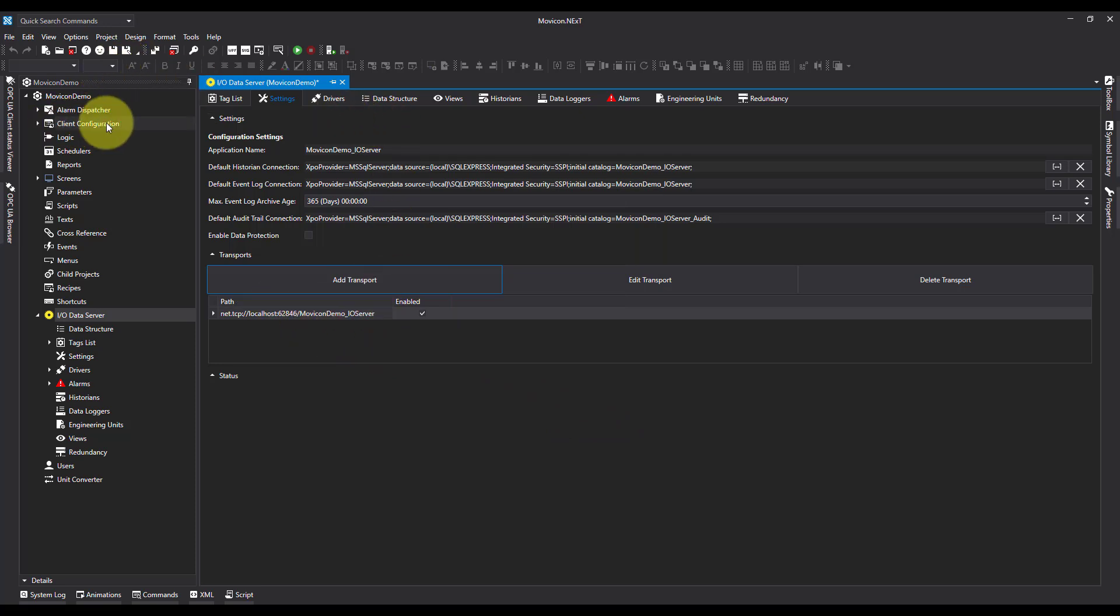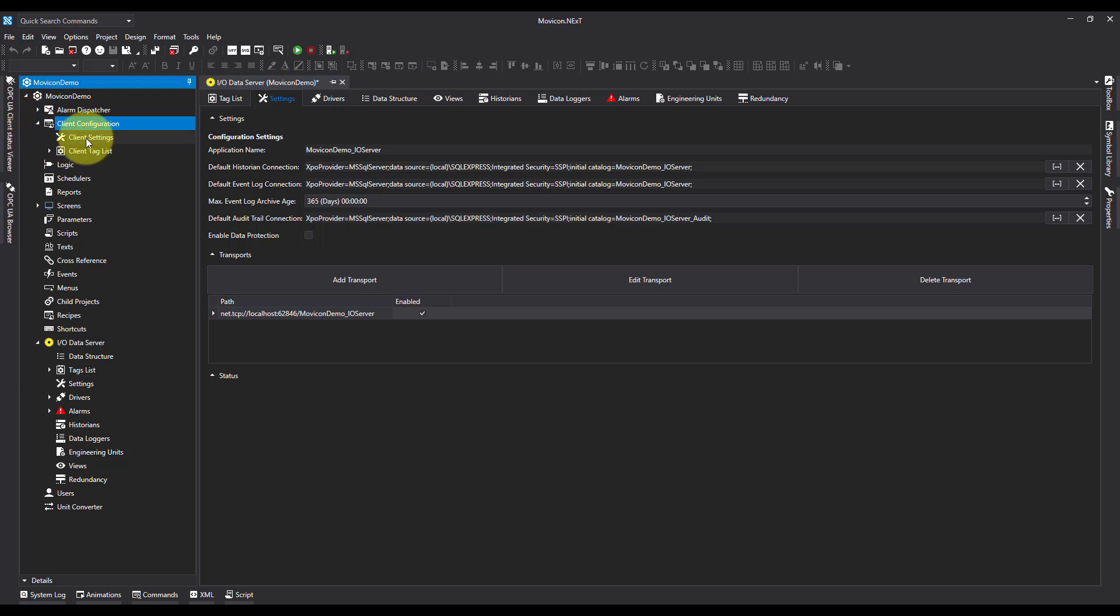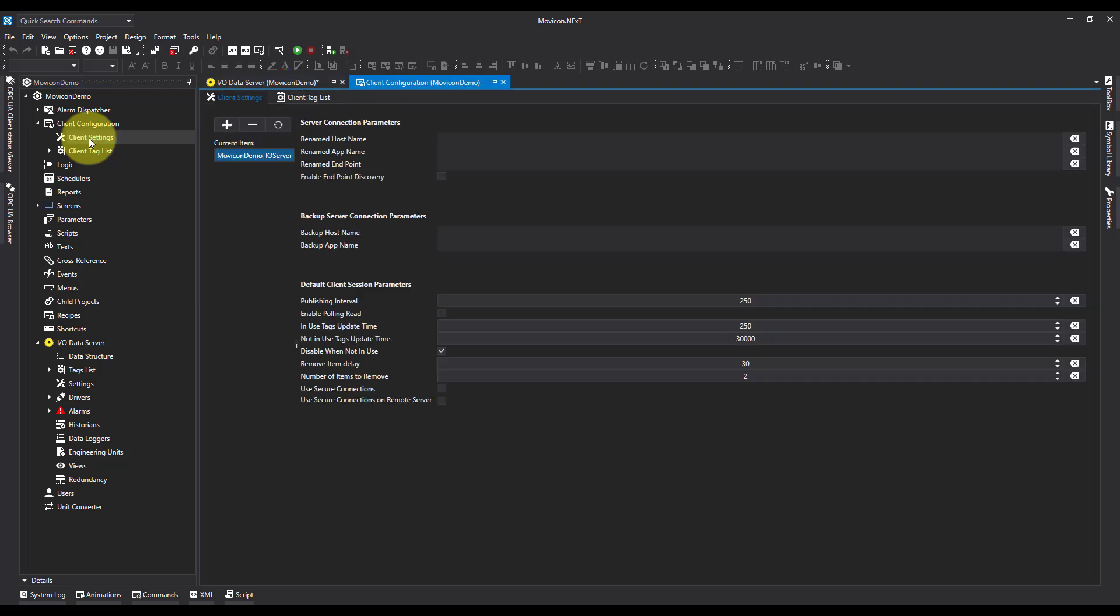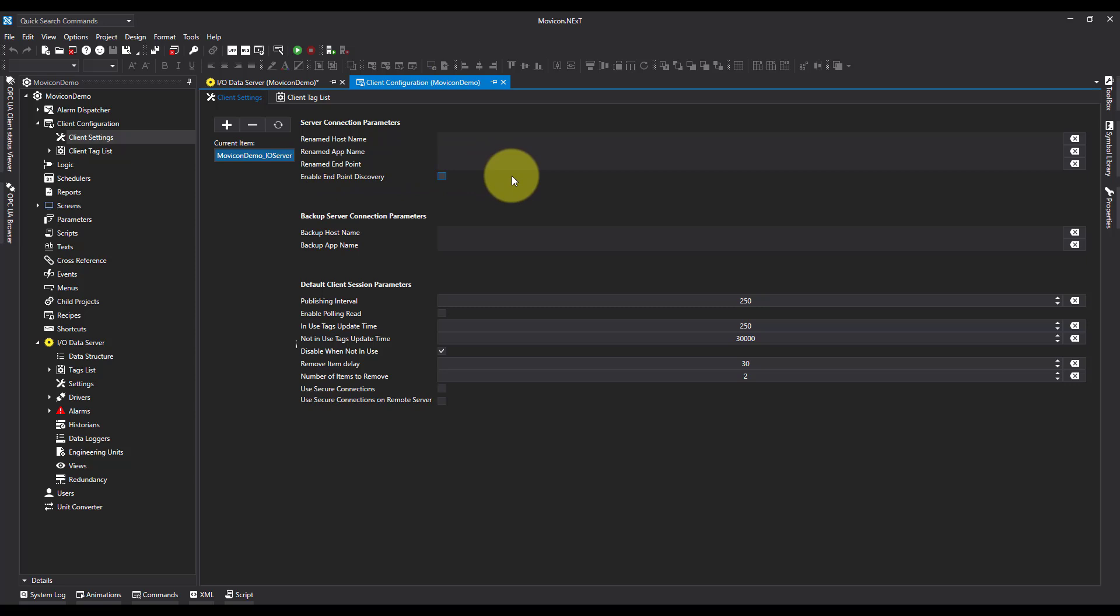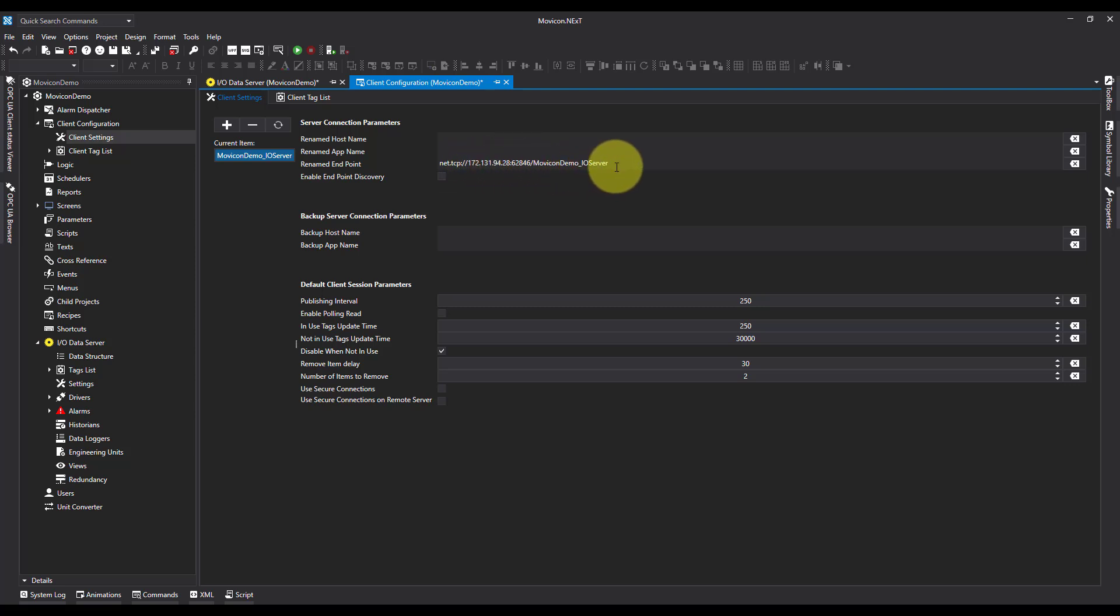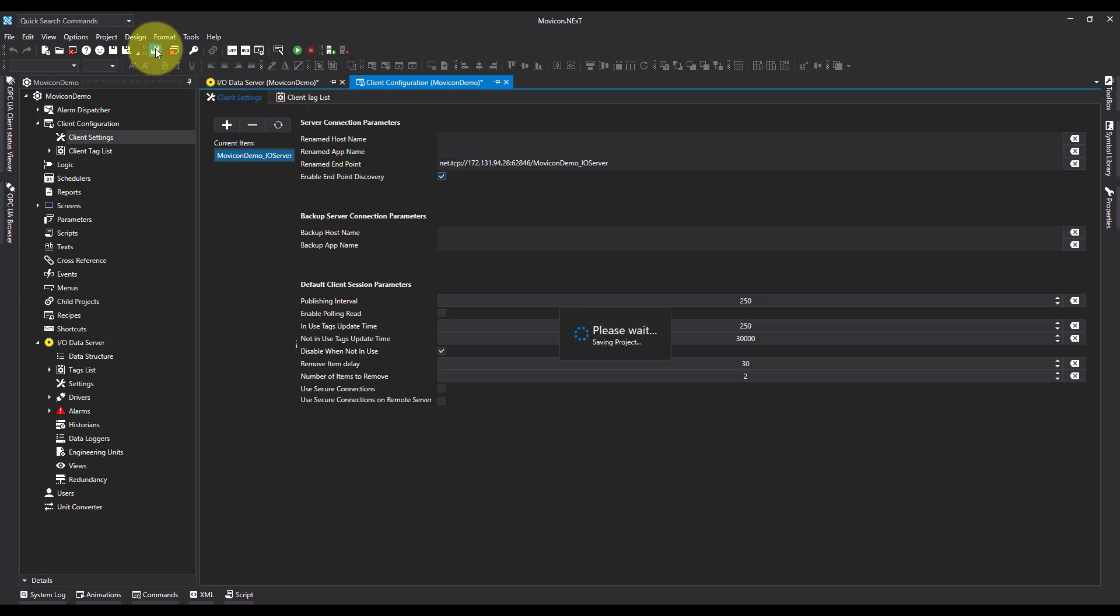Now, I'm going to come up to Client Configuration, to Client Settings, and I'm going to come to my Renamed Endpoint. What we're effectively doing is, we're telling the client where to look for the tags. And that's what our Renamed Endpoint is. So I'm going to paste in the new address, and I'm also going to say Enable Endpoint Discovery. I'm going to go ahead and hit Save All.